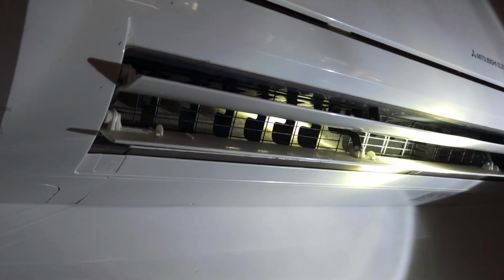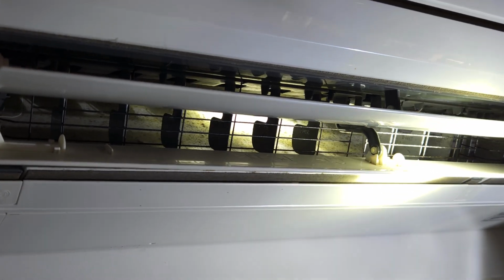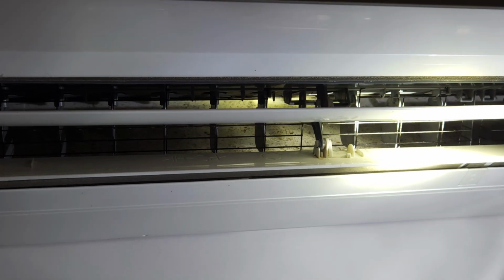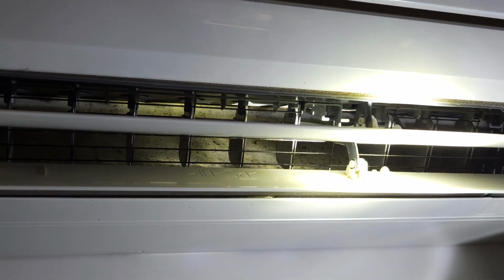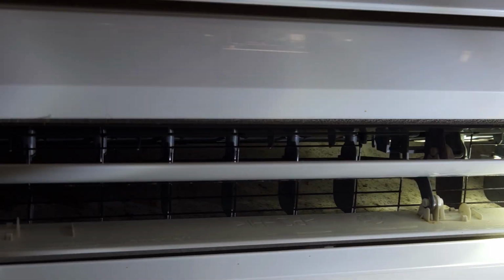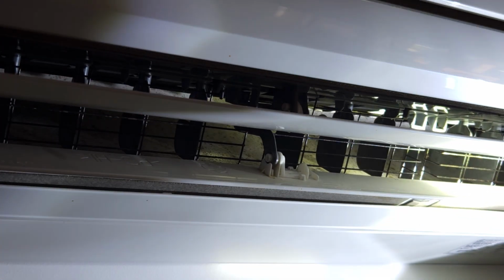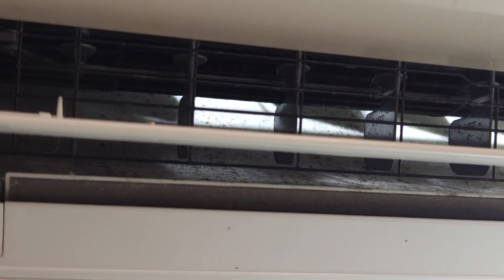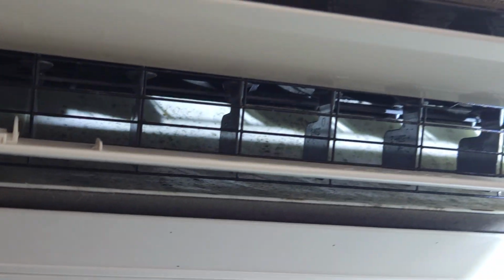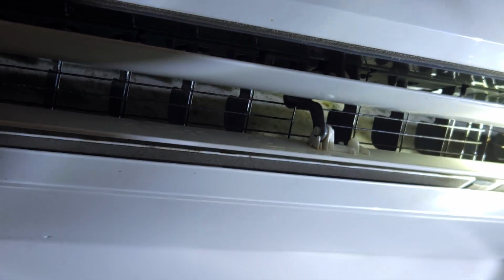This is a pretty prime example. Can you see that in there? If you can see on the camera, there's potential mold in that unit. So that's not only dust. There are black patches in it. This is in the heat pump, what we call heat pumps in New Zealand, or air conditioning units. If you look right up in there, there's a barrel fan that spins the air around, and you can even see furry stuff growing on it. We'd call that potential mold until we actually test it.